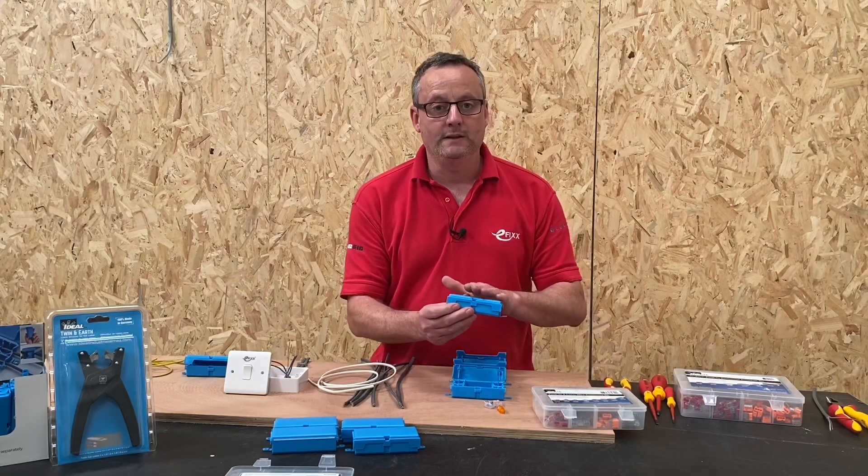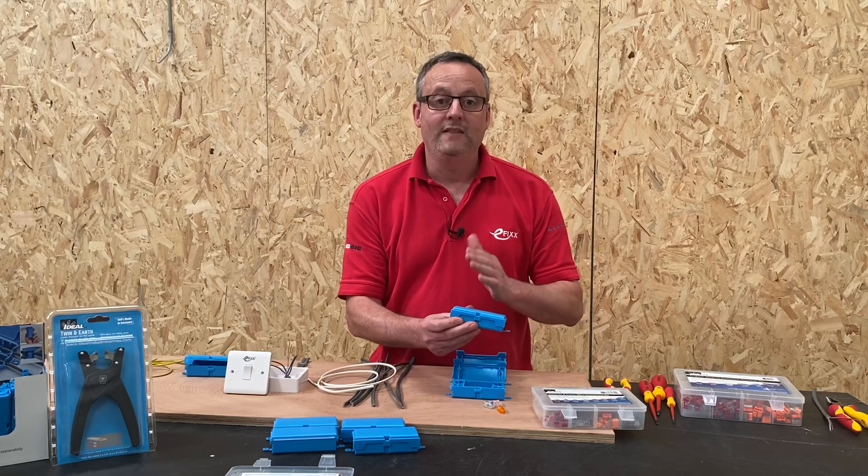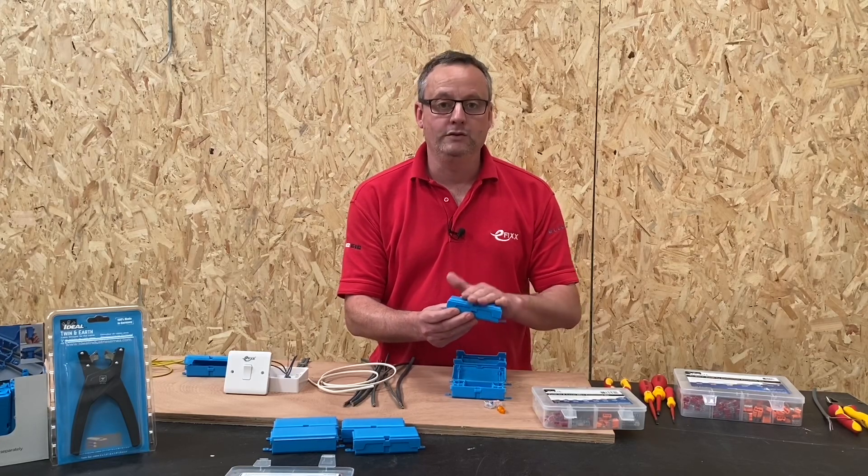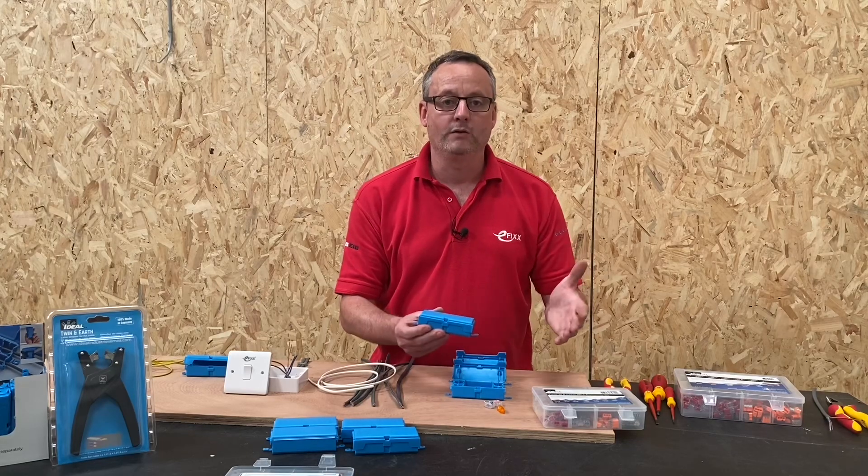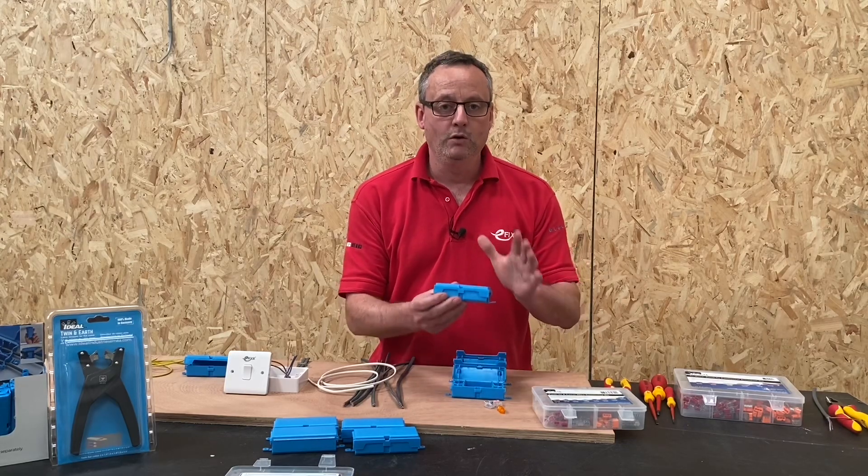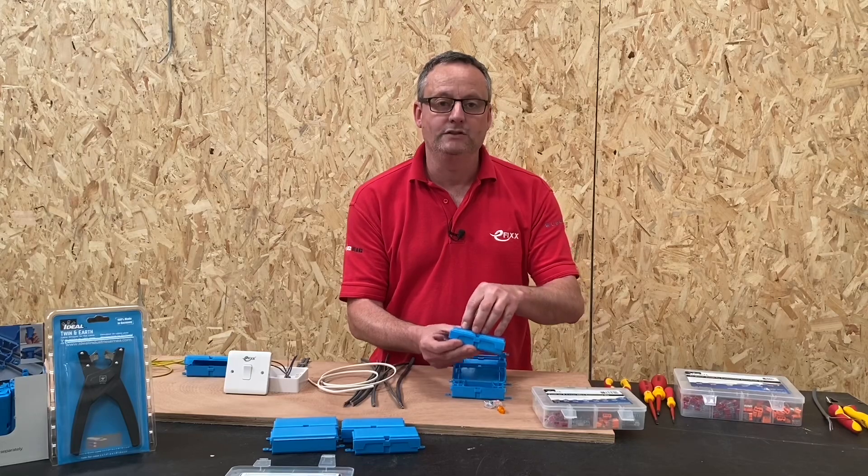However, as soon as we insert them into this lighting joint box, they become rated only at 16 amps. So we couldn't use this box, for instance, to extend a ring final circuit or a cooker circuit. We'll look next at how we're going to make some of the connections within this box.